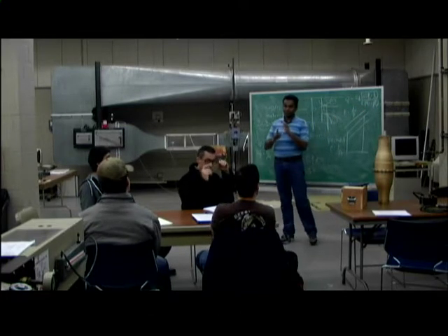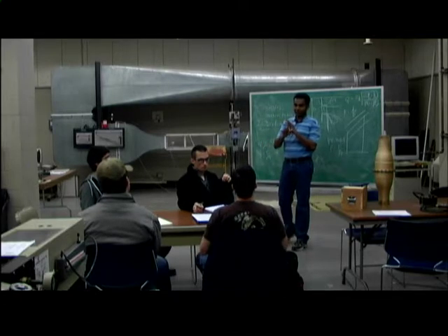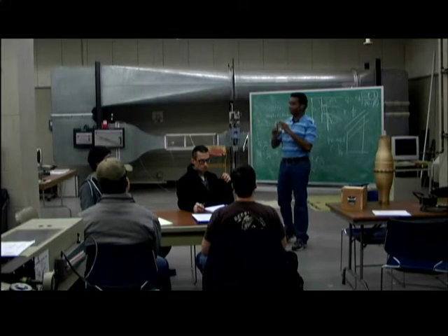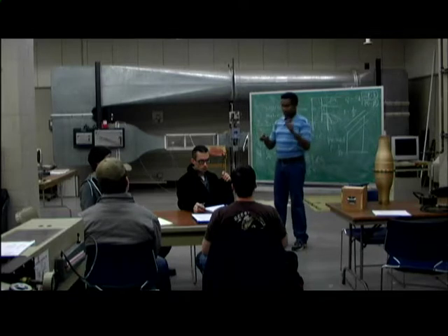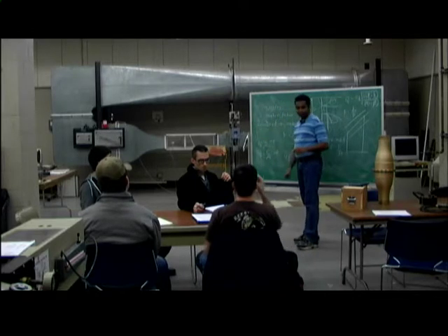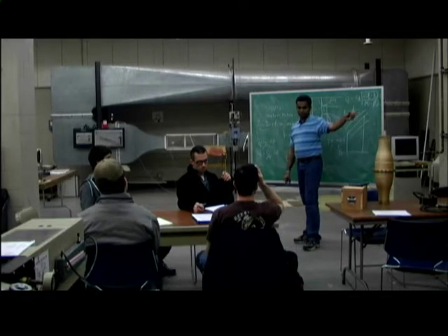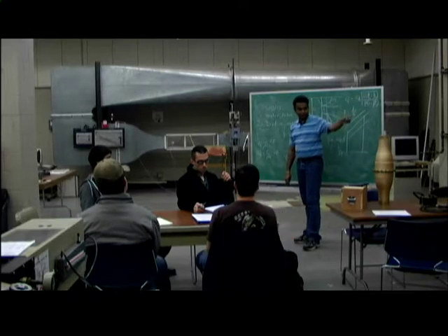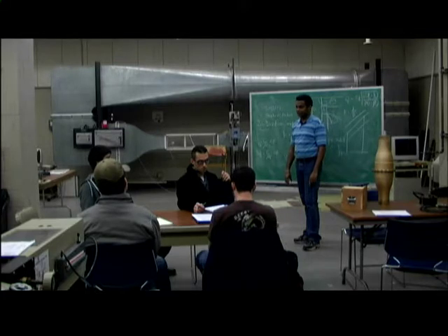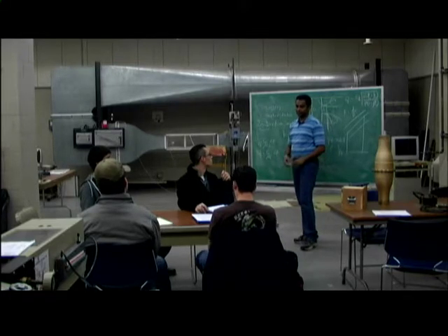So you need to have 3 manometers basically, right, in the system. When you go there, you can see it. And then you have 2 temperature gauges to measure the temperature here, and you have to take that temperature measurement and the barometric reading. Okay? That makes sense? Alright.